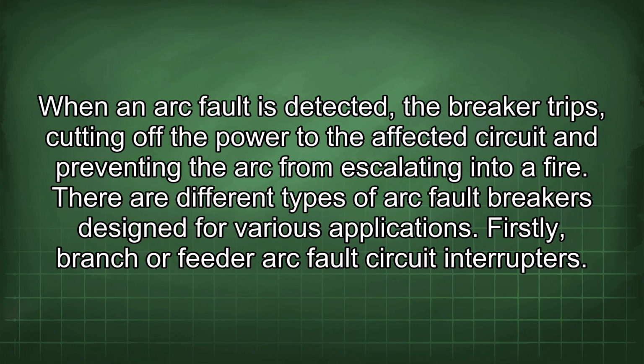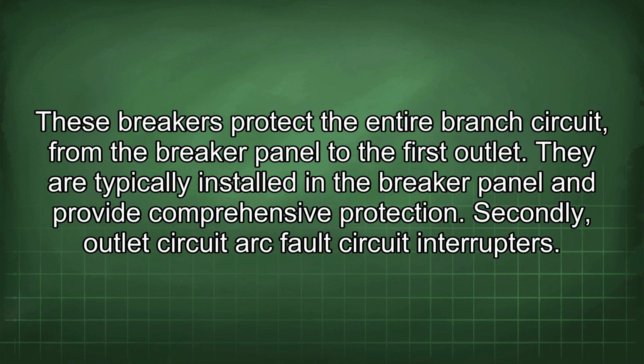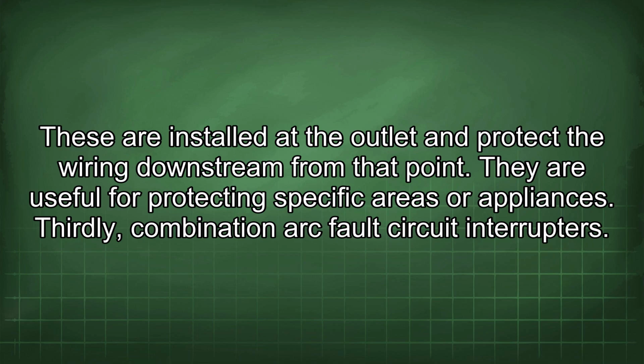Firstly, branch or feeder arc fault circuit interrupters. These breakers protect the entire branch circuit from the breaker panel to the first outlet. They are typically installed in the breaker panel and provide comprehensive protection. Secondly, outlet circuit arc fault circuit interrupters. These are installed at the outlet and protect the wiring downstream from that point. They are useful for protecting specific areas or appliances.